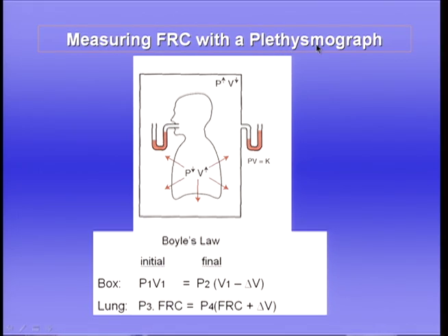It's not used quite so much now because we have another method of measuring these lung volumes, and I'm going to talk about it now. It's more complicated, at least to explain, but it's actually simpler for the subject to do. And that is the technique using a body box, or to give it a fancy name, the plethysmograph. The body box is simply an airtight box, rather like an old telephone booth. And the subject sits inside that, and we measure the pressure inside the box with a sensitive manometer.